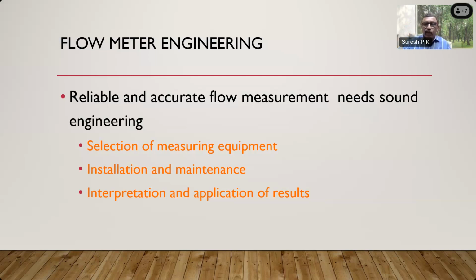You have to properly select the flow meter and place it where the flow measurement can be taken. If the flow is not proper, put in some upstream and downstream lengths, or you can put in flow straighteners. If the flow is not straight, you can straighten it out. But flow straighteners are always costly, because you lose pressure of the fluid. The pressure is generated by the pump, so the pump has to be selected in such a way that it accommodates the pressure loss also. So the pump cost goes high, and the pump running cost goes high. All these things are a combination; they are mutually dependent, not independent.